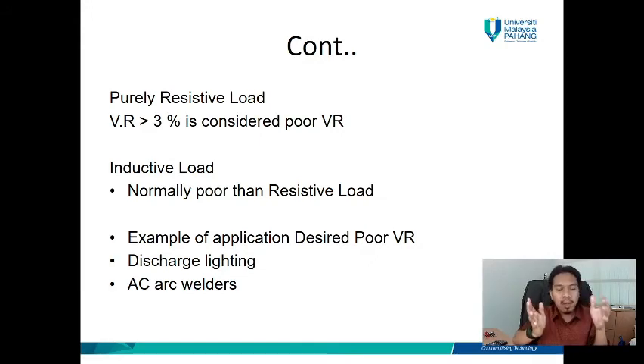The value of VR depends on the type of transformer load. For example, if purely resistive load, the value of VR is more than 3%, but it is still considered a poor VR. If we have an inductive load, the value of VR becomes worse, normally worse than resistive load. So loads such as discharge lighting, a welder, induction motor, fan, or any load that has a coil winding will give a poor VR value for the transformer.